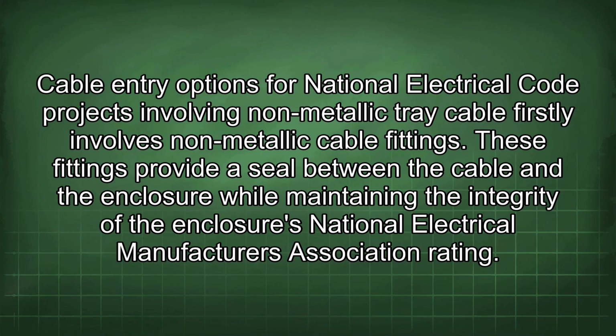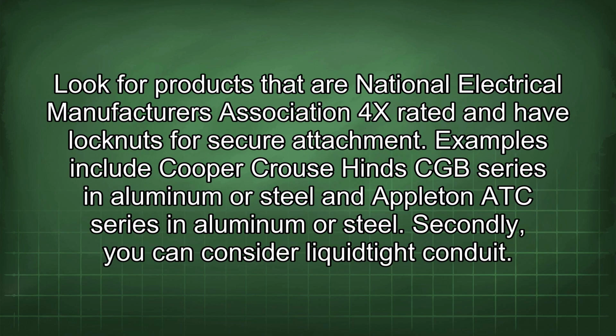Cable entry options for National Electrical Code projects involving non-metallic tray cable. Firstly, it involves non-metallic cable fittings. These fittings provide a seal between the cable and the enclosure while maintaining the integrity of the enclosure's National Electrical Manufacturers Association rating. Look for products that are National Electrical Manufacturers Association 4X rated and have lock nuts for secure attachment. Examples include Cooper Crouse-Hinds CGB series in aluminum or steel and Appleton ATC series in aluminum or steel.